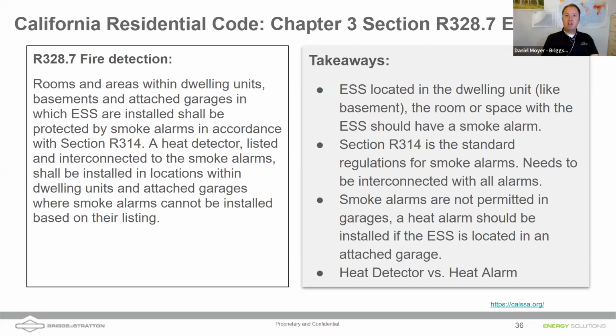This is a big one: smoke alarms. When you put in one of these systems, you have to have a smoke alarm. If you put a battery in a garage, well, smoke alarms aren't listed to be installed in a garage. If you buy a new smoke alarm, it'll say right in the instructions. In fact, I just put in one of those carbon monoxide smoke alarms, and I'm one to read the instructions, and it says don't put it in a garage because the ambient temperatures expected there exceed the rating of that smoke alarm.